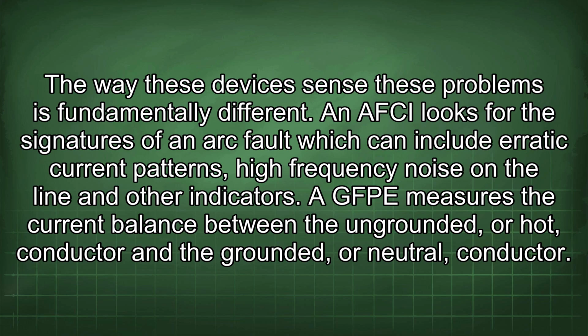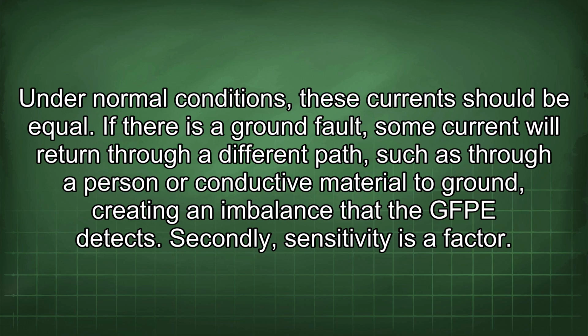An AFCI looks for the signatures of an arc fault, which can include erratic current patterns, high-frequency noise on the line, and other indicators. A GFPE measures the current balance between the ungrounded, or hot, conductor and the grounded, or neutral, conductor. Under normal conditions, these currents should be equal. If there is a ground fault, some current will return through a different path, such as through a person or conductive material to ground, creating an imbalance that the GFPE detects.